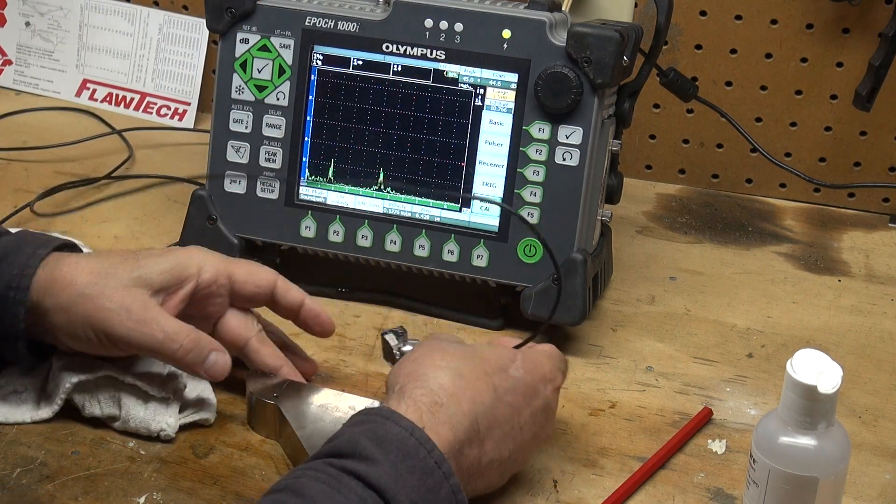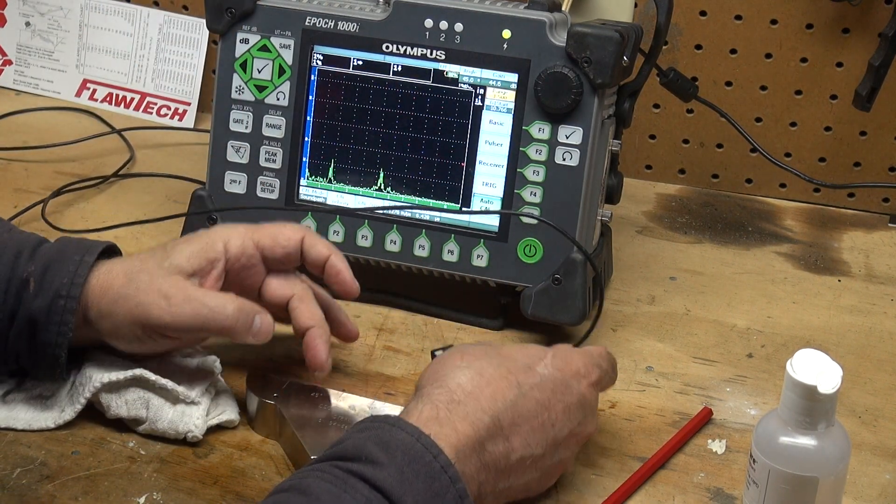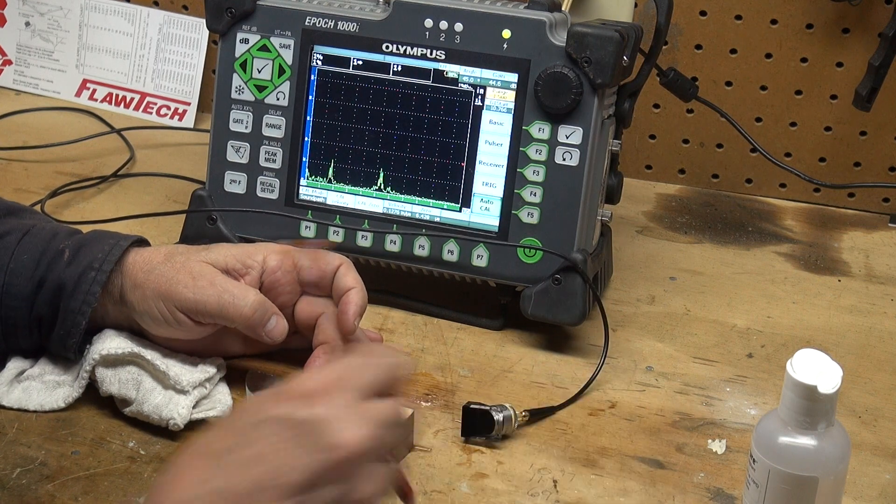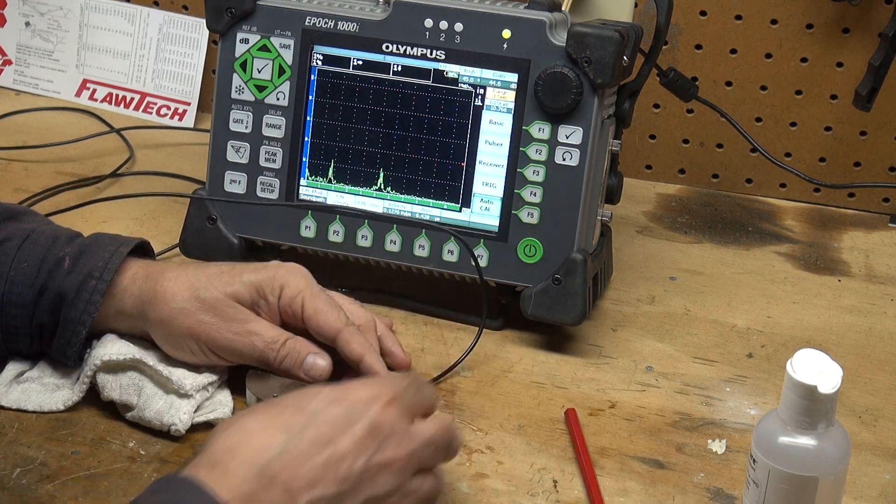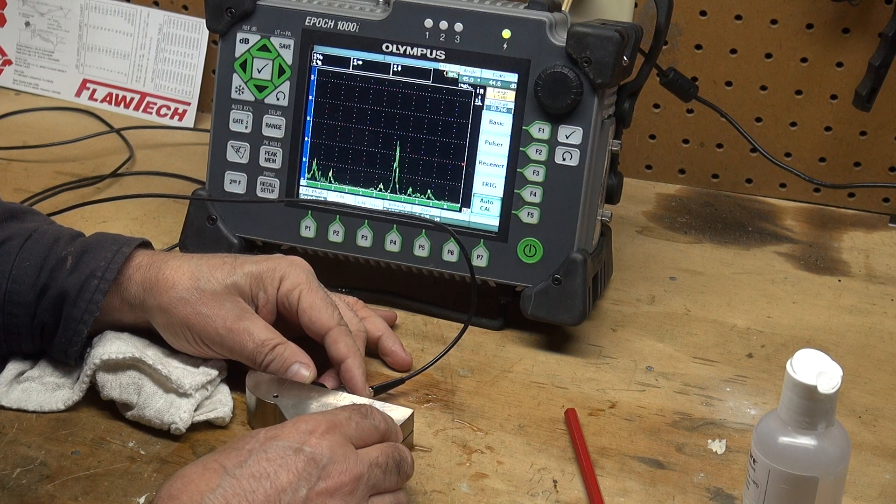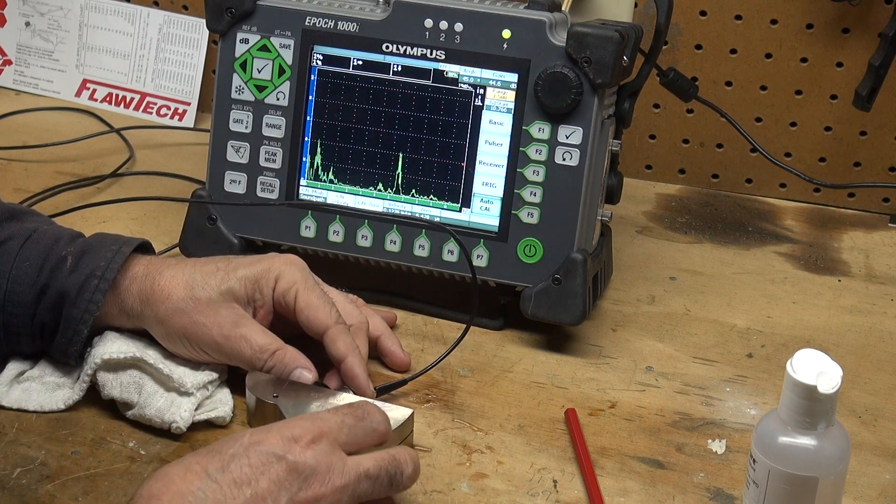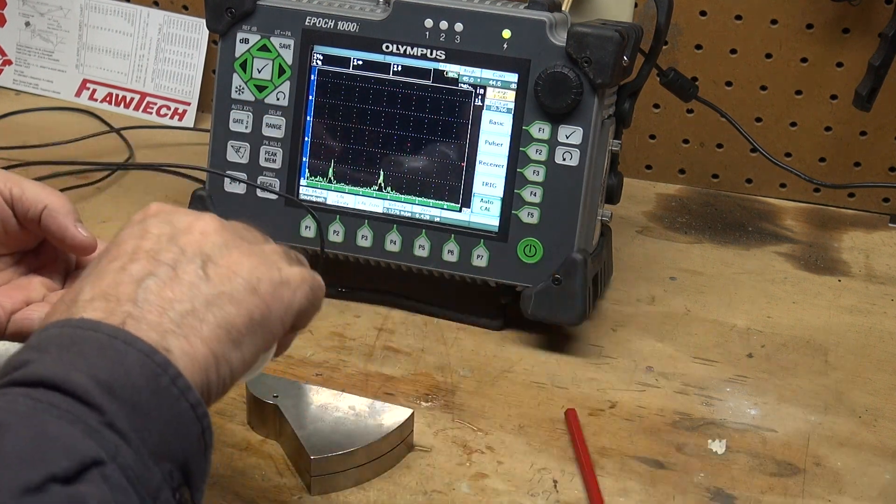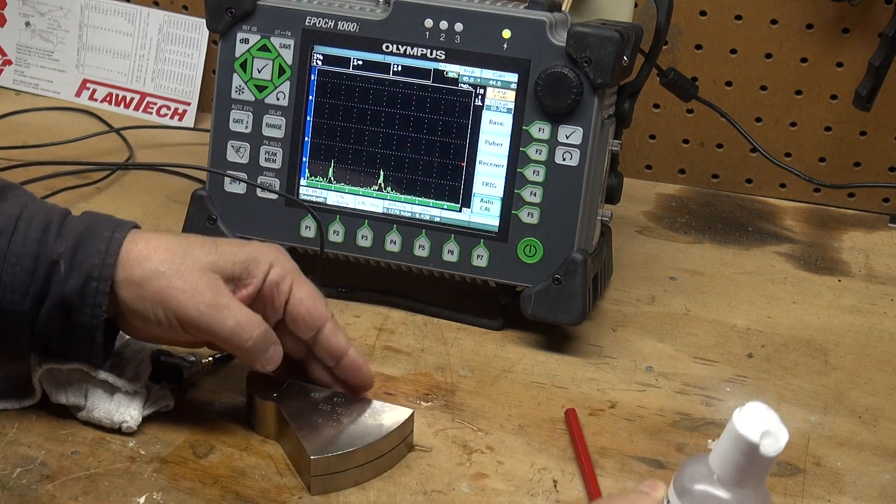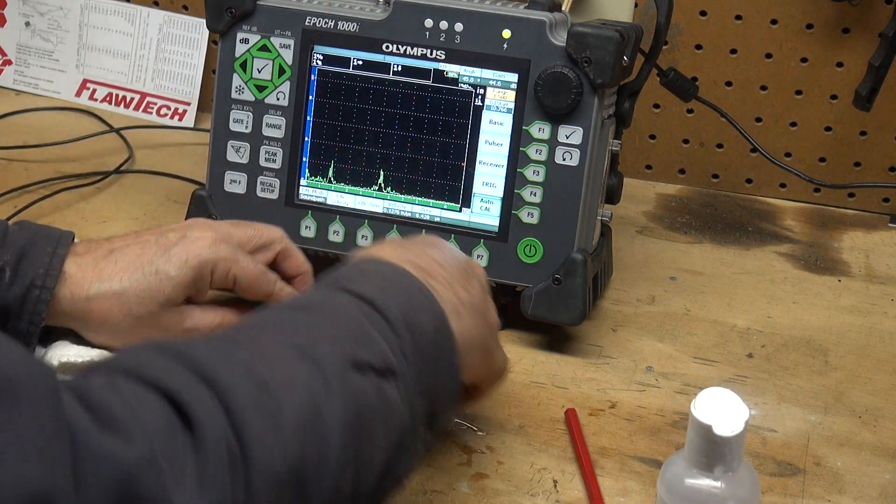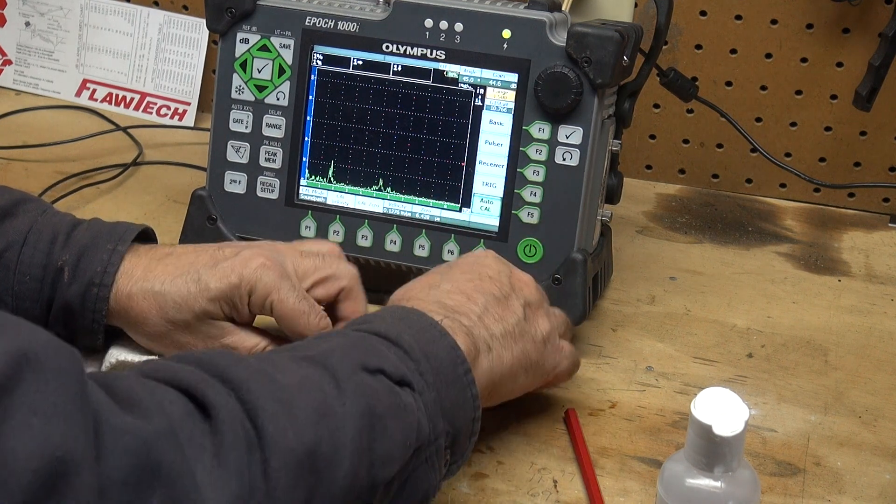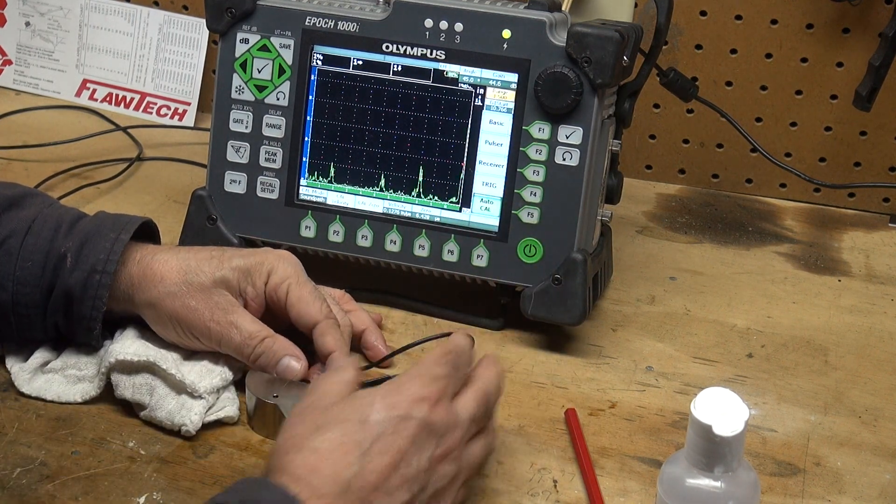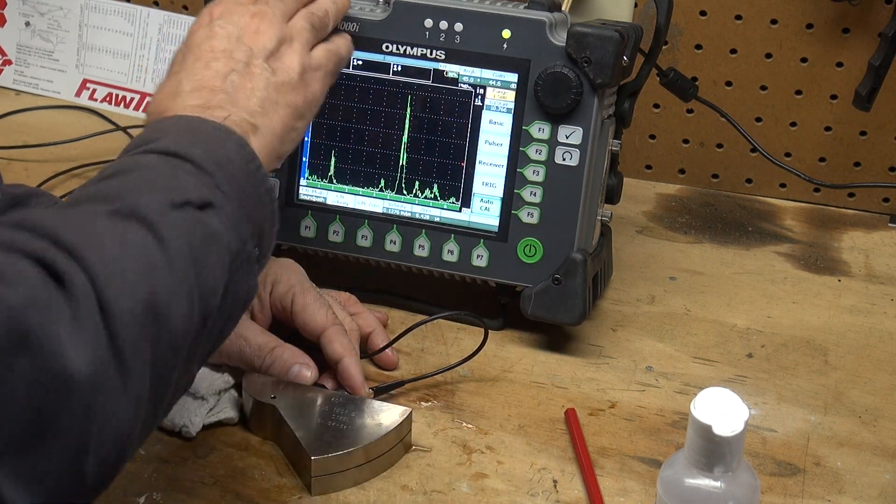My transducer, this is a 45 degree, so here's 45 degrees up to 70. So I'm going to put it about 45 degrees and when I see that signal popping up, let me put a little more couplant on there, running it dry.